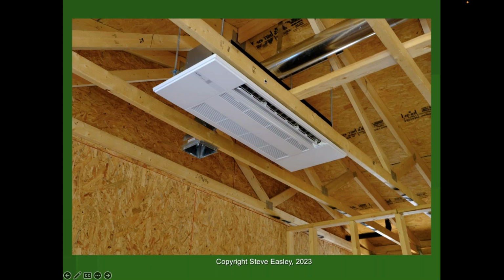And the beauty of these one-way cassettes is they only protrude down from the ceiling about a half an inch. They're all 100% serviceable from below. They have a condensate pump that will pump the condensate out to the outdoors. So I don't have to have any ductwork, and each room can have its own zone. So I can control the temperature of each room, and you can put up to 8 of these on one condenser. This inverter-driven system allows us to have very individualized zone control and draw at much lower amperages than your traditional heat pump would. So it makes it much more friendly to the grid. And these things are incredibly quiet.